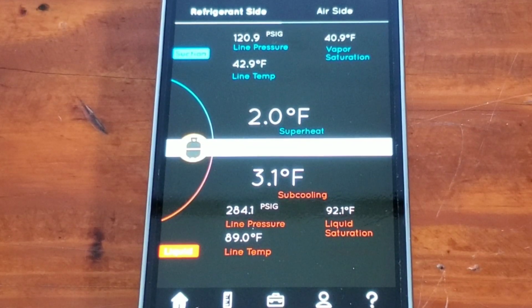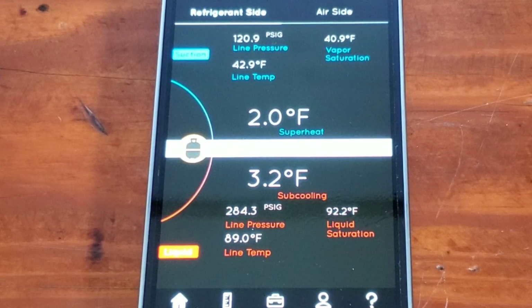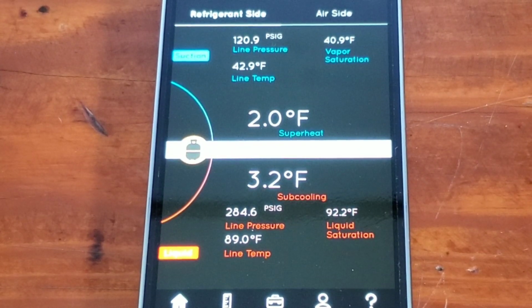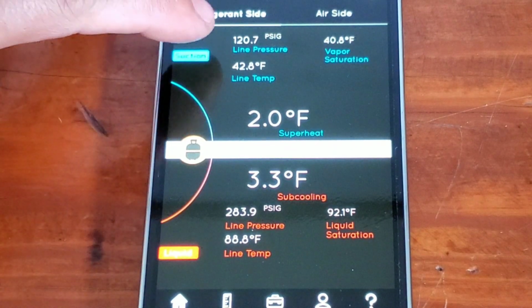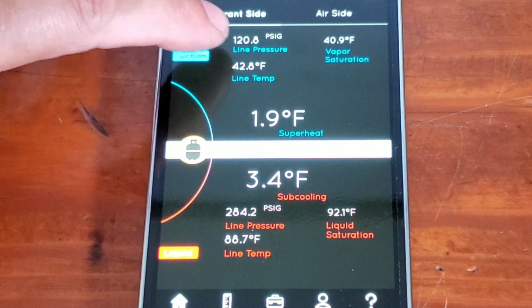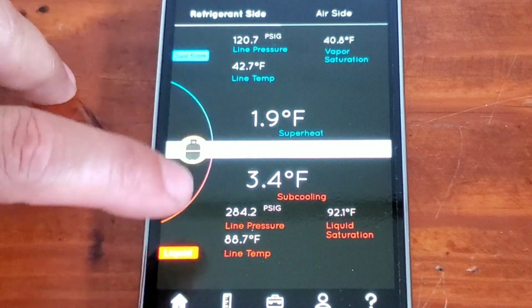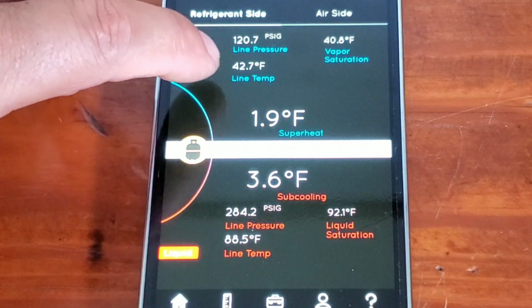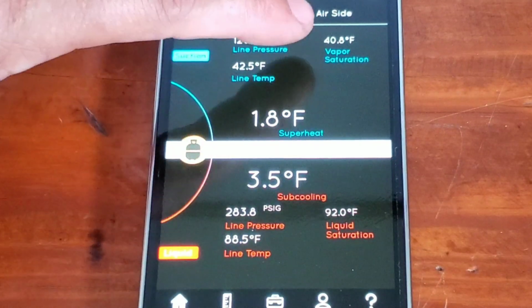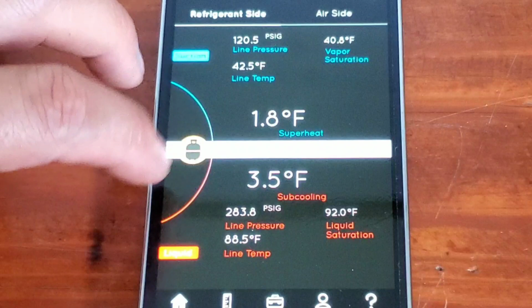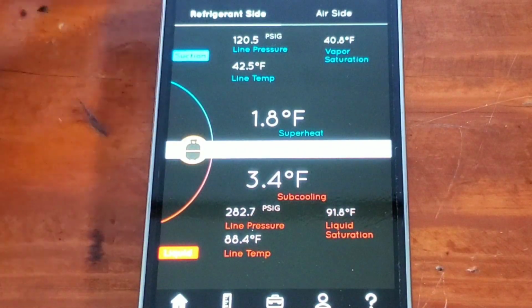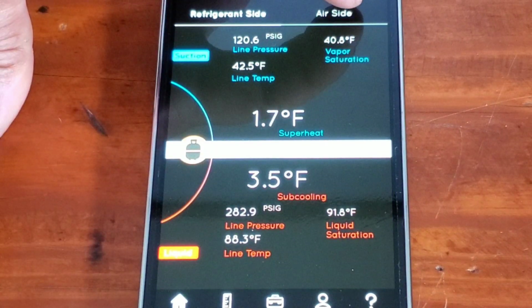Now we have the HUB6 probes hooked up to my system at the house. It's just a 10-year-old 13-seer Bryant system, piston metering device by the looks of it, possibly an oversized piston. But you can see, super easy format to read. We have our low side pressure 120, high side 284, our line temperatures, our saturation temperatures, and then our superheat and subcooling.